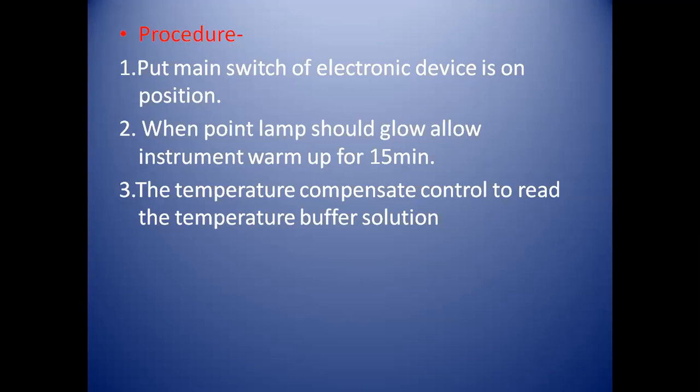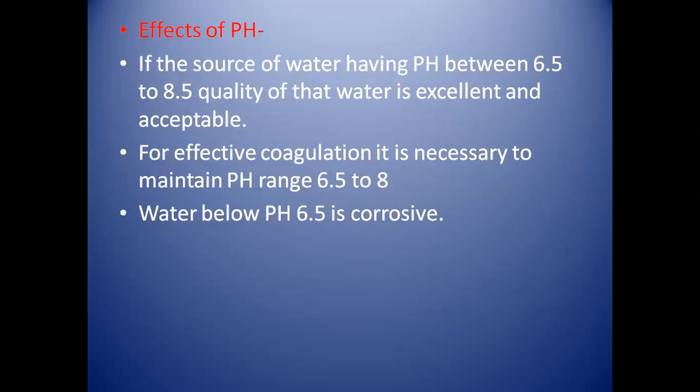Then use the temperature compensation control to read the temperature of the buffer solution, or the solution which is used for taking the pH test.